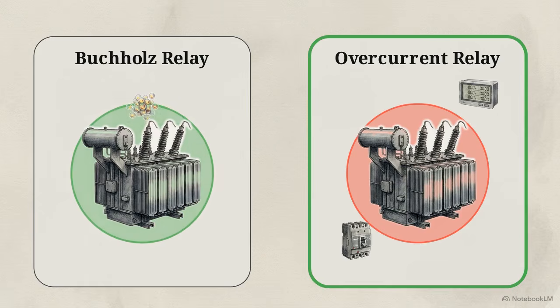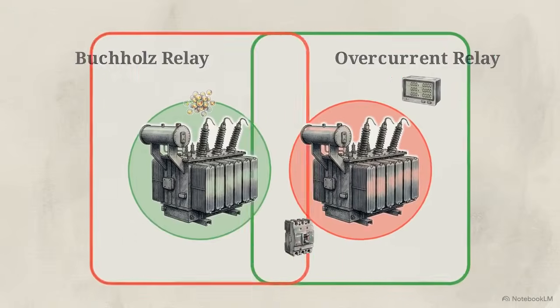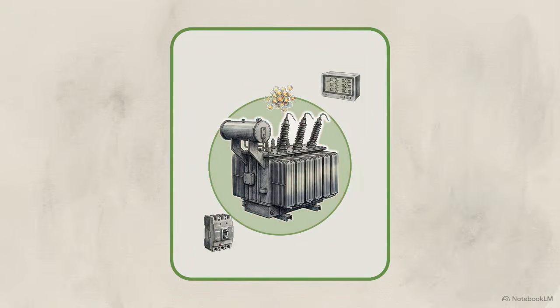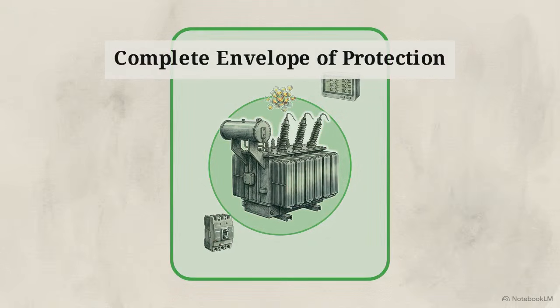Conversely, the Buchholz relay is perfectly tuned to catch that internal chemical decay, but it is physically disconnected from the electrical grid. It cannot detect a massive short circuit occurring outside the tank. By overlaying these two highly specialized systems, engineers eliminate both blind spots, creating a complete, overlapping envelope of protection.